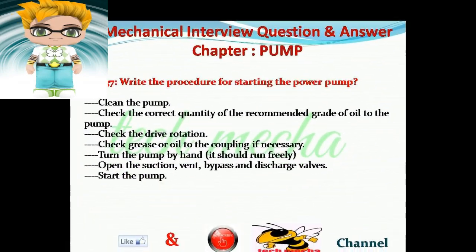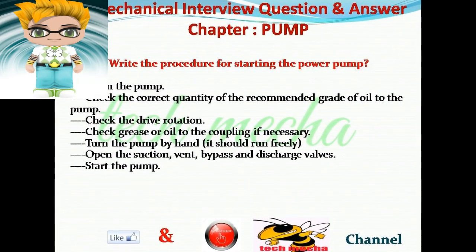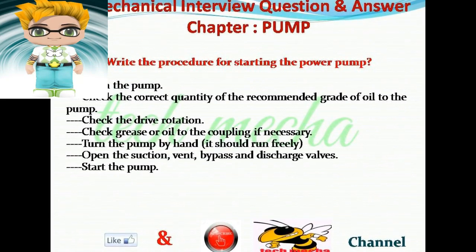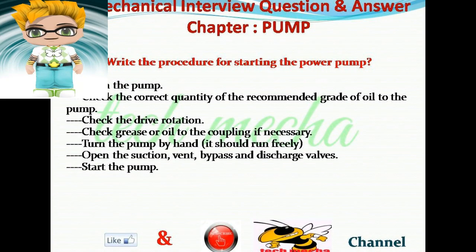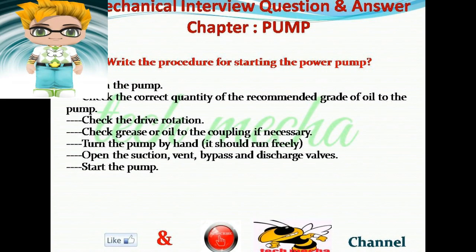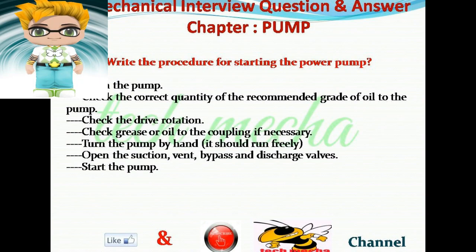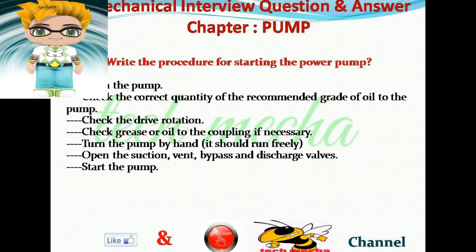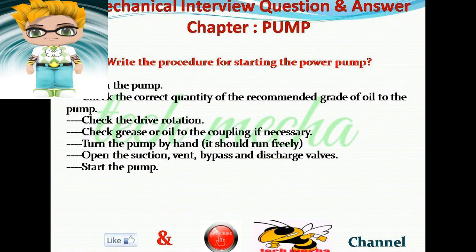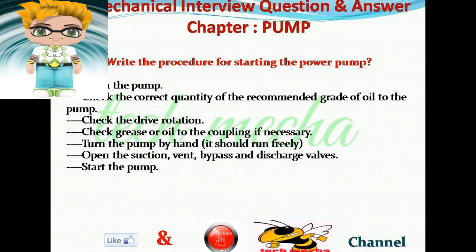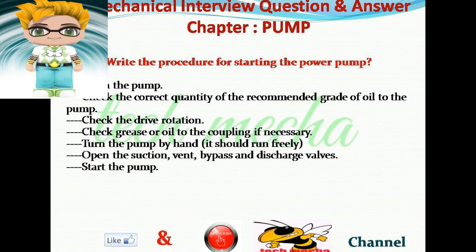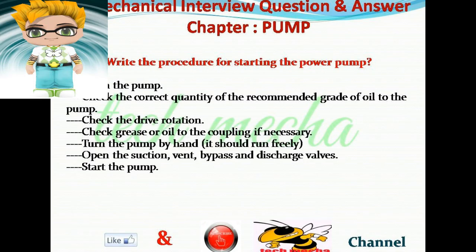Question number 37: Write the procedure for starting a power pump. Answer: Clean the pump. Check the correct quantity of the recommended grade of oil. Check the drive rotation. Check grease or oil to the coupling if necessary. Turn the pump by hand — it should run freely. Open the suction, vent, bypass, and discharge valves. Start the pump.